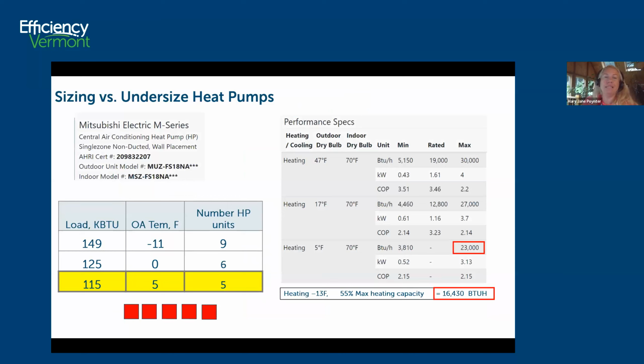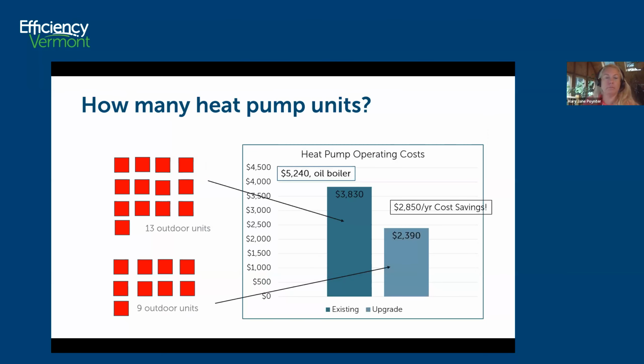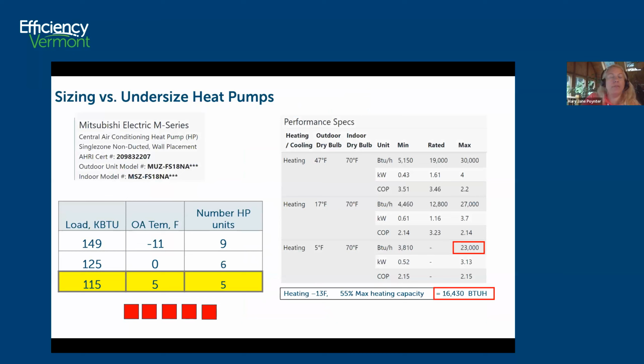Now comes the question of sizing versus undersizing. So if you were to try and size for -11, I figured we would need about 9 heat pumps. That's at the lower load, 149. So 149 is the load that I calculated once we did the air sealing and insulating. And if you want to satisfy 99% of the load, you need to have enough heat pumps that can meet the load of 149 with maybe just 1% of the time with the oil boiler.